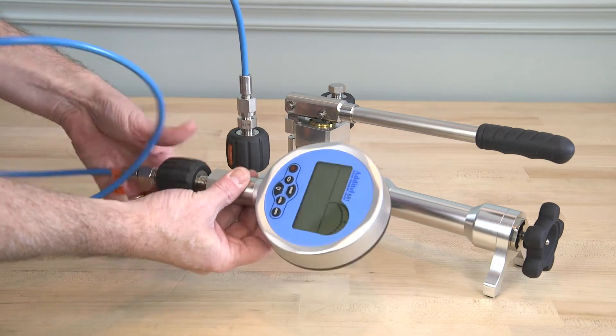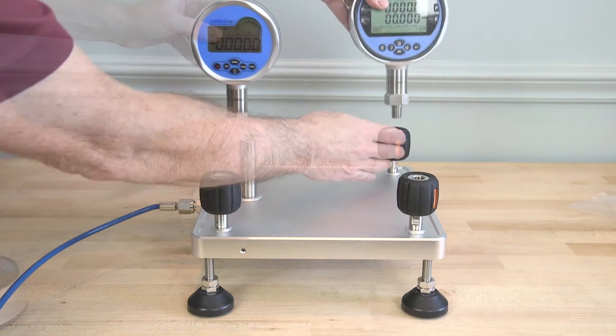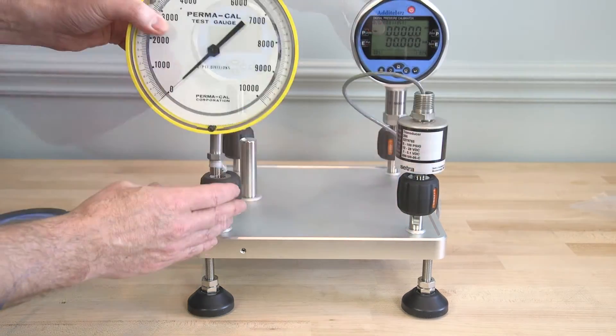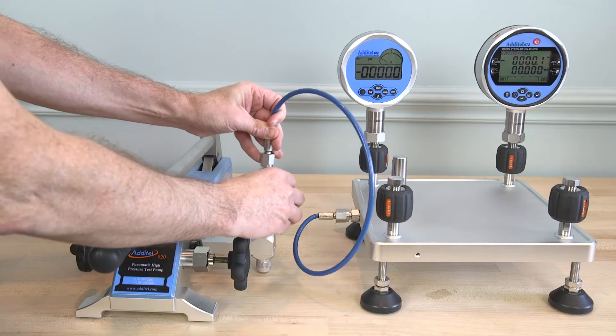Additel quick connectors allow for hand-tight connection without the need for wrenches or Teflon tape. Additel 120 series pressure manifolds are designed for expanding pressure test ports during pressure calibration. The Additel 121 pressure manifold is used for pneumatic pressure calibration up to 3,000 PSI or 200 bar.